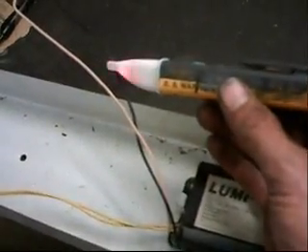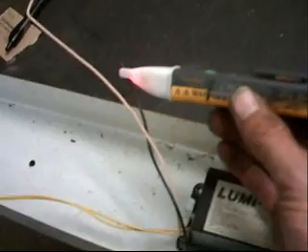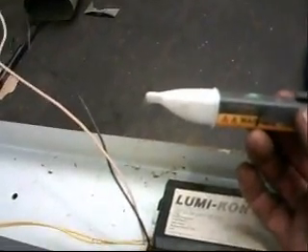After you have removed your cover from your fixture, you are going to want to put your tester on your black wire, which should be hot. I always test to make sure the power is off. If it is on a switch, it's a good idea to go ahead and turn the breaker off, because if somebody comes along and turns the switch on while you are working on it, you are going to get zapped.